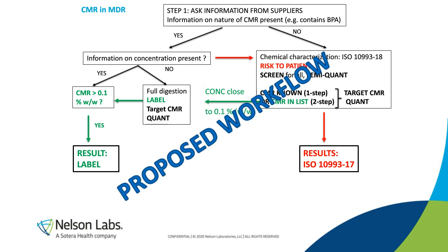And I would propose to really go back to the supplier and say, look, we found this particular CMR in your device. We know it's there. You are now being held responsible as a supplier to identify these kinds of compounds. So please let us know the total amount there, because if not, you're kind of stuck using an extractable semi-quant, or even if it's quant, it's still an extractable amount and not the full concentration in the device.